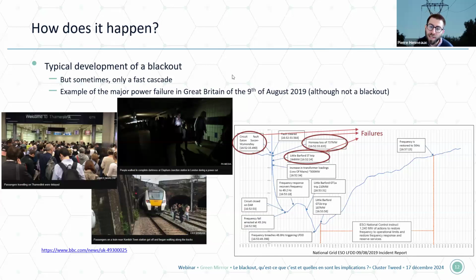Sometimes you have only a fast cascade, because you directly trigger an electrical instability. You have an illustration of that in Great Britain on the 9th of August 2019. They had a major power failure, although it was not a blackout because the transmission system kept its integrity, so not a blackout in the definition that I gave at the beginning of this presentation. But the transport system was strongly impacted, and so you can see here trains stopped, Clapham Junction in the dark in London, and so on. And so what happened there?